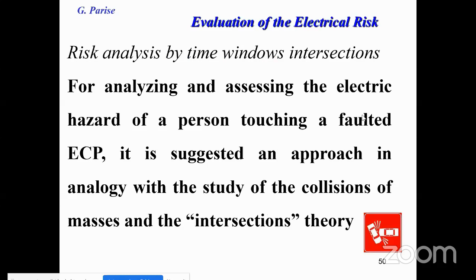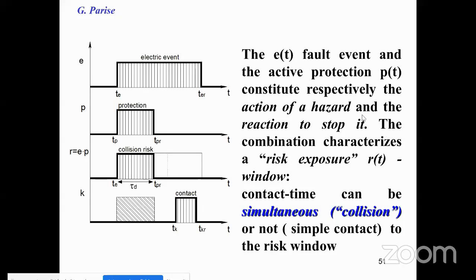So at the end, we have to do a risk analysis by time windows intersection for analyzing and assessing the electric hazard of a person touching a faulted exposed conductive part. It is suggested an approach in analogy with the study of the collisions of masses and the intersection theory. A collision happens when two masses go to the same point at the same time. And so when we have to consider a fault event and an active protection, they constitute respectively the action of a hazard and the reaction to stop it.